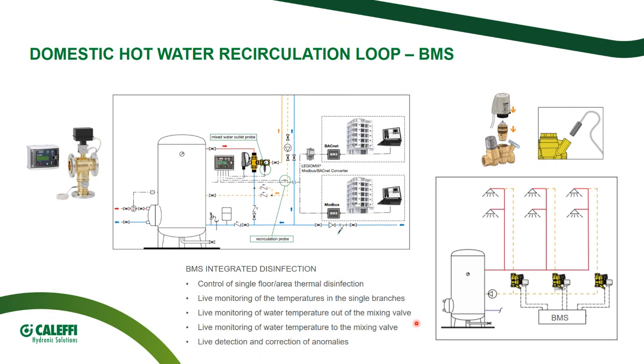A special overview on the combination of a digital mixing valve and electrothermally actuated thermostatic balancing valve, because this digital mixing valve can be connected to the BMS, but also the electrothermal bypass element can be connected to the BMS system. And if you remember, we have a pocket. If we replace the temperature gauge with a temperature sensor, we are giving the customer a complete package in order to control and perform the thermal disinfection throughout the building, controllable remotely with BMS.